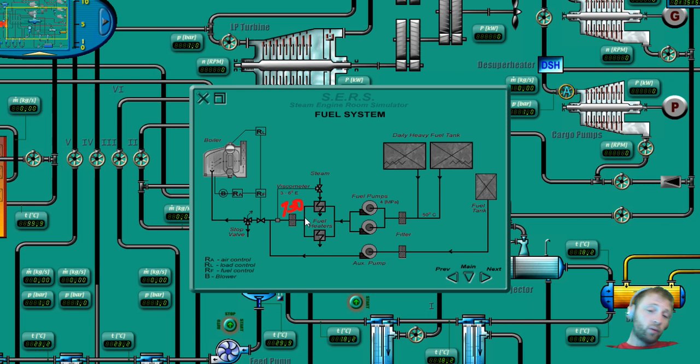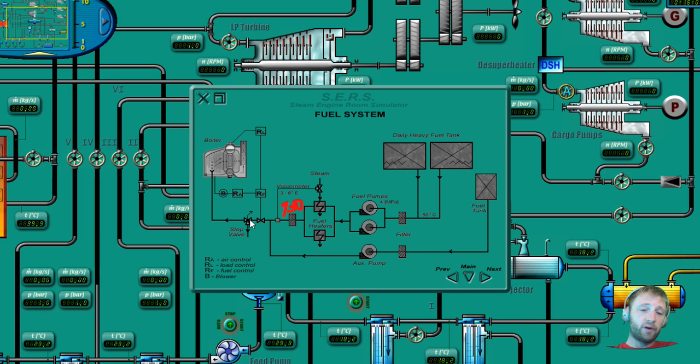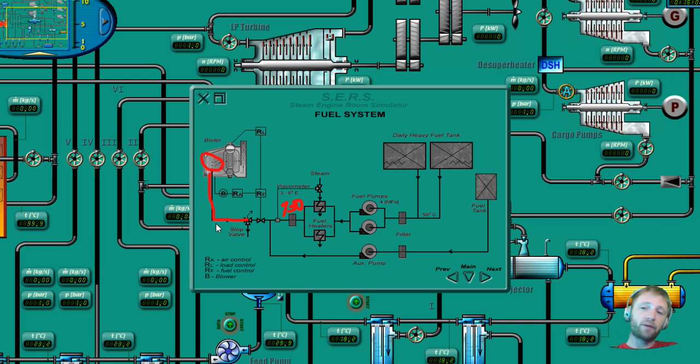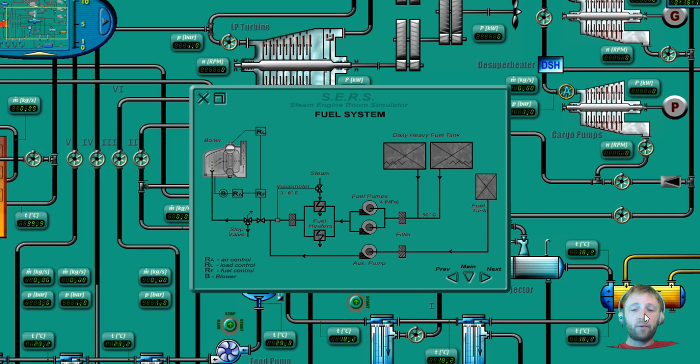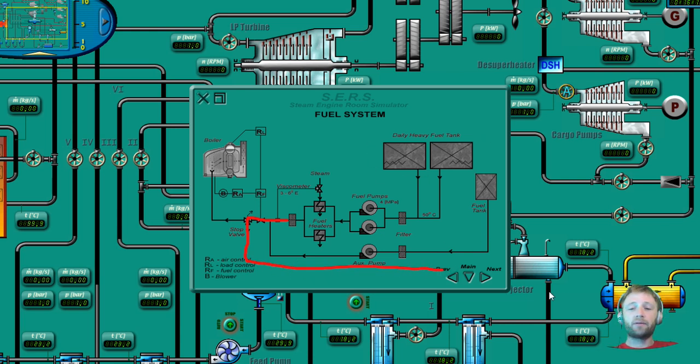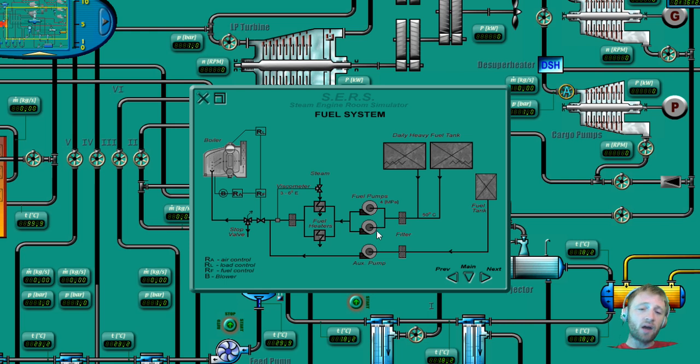So after the fuel heaters and viscosimeter will give the signal to the steam for heating this fuel, let's say that we achieve 130 degrees here. Our fuel oil will pass again some filters and then will be sent to the boiler and to our burners which is located here. We have four burners in total.